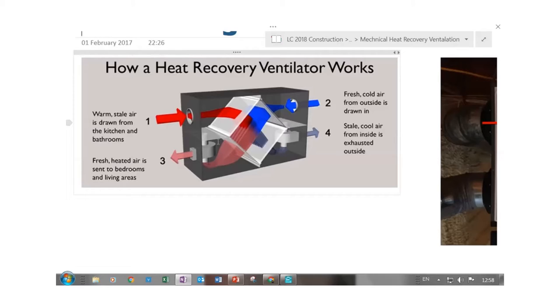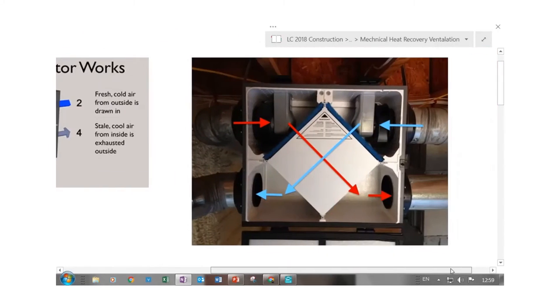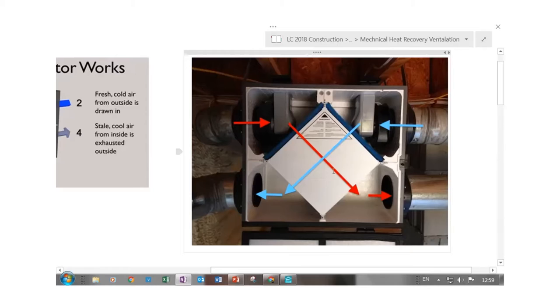Because of this system, you'll have no radiators, so when building the house you won't need a plumber to install a radiator in each room. Looking at pictures of the unit — the red arrows show the direction of air. This is where all the metal plates are contained, where all the heat transfers into the plates, and then the cold fresh air hits those plates and gets warmed up.